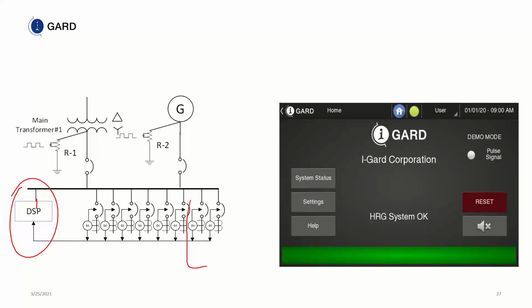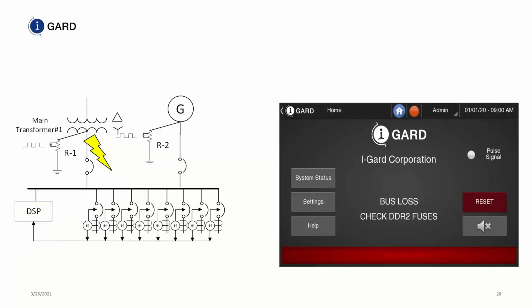And we monitor the current. So this is why we tell you we can determine if there's a fault, what phase the fault is on, and what feeder the fault is on, because we're monitoring the current going this way. If we see the voltage escalate and there's no current flowing, we tell you that there is a bus fault on the system. That means the fault is on the line side of all those feeders. So it's either in the transformer or it's in the generator, and seeing as only one of those breakers is going to be closed at any one time, you know it's going to be between here and here.